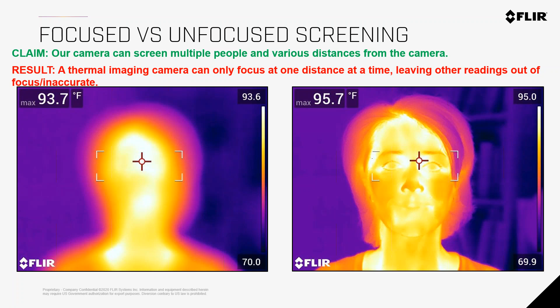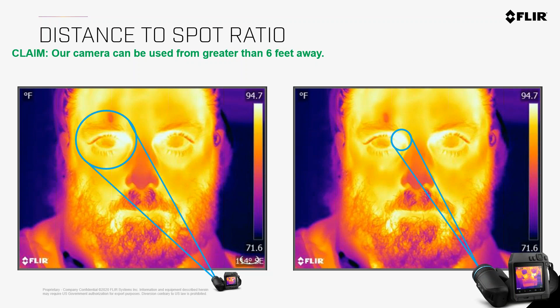Another part of screening and the cameras that you want to be aware of is the distance to spot ratio. There are some claims out there that our camera can be used from greater than 6 feet away. Here is an example of what spot to distance ratio is. The image on the left has a camera that is a lot smaller compared to the camera on the right, indicating that it's further away from the subject.